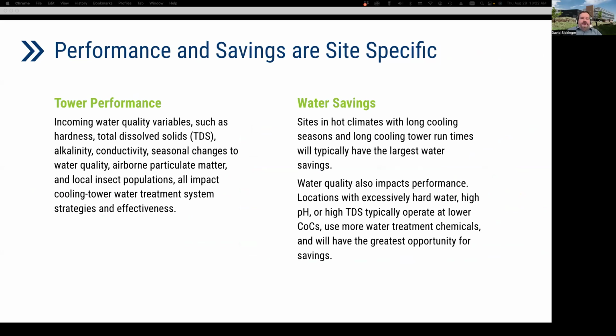So performance and savings are also site specific in terms of cooling tower performance. Incoming water quality can vary, such as hardness, total dissolved solids, alkalinity, conductivity, airborne particulate matter, and these all can have seasonal changes as well. And all this combines to impact cooling tower water treatment system strategies and effectiveness. In terms of water savings, sites in hot climates with long cooling seasons and long tower run times will typically have the largest water savings. And again, locations with excessively hard water, high pH, and high total dissolved solids typically operate at lower COCs and use more chemicals, so they have the greatest opportunity for savings.